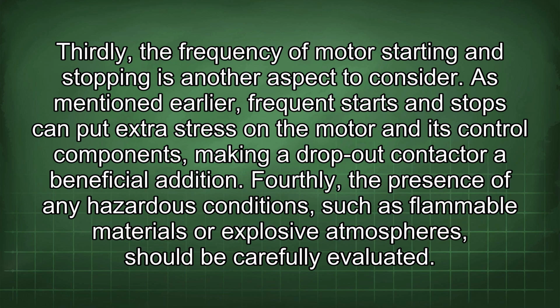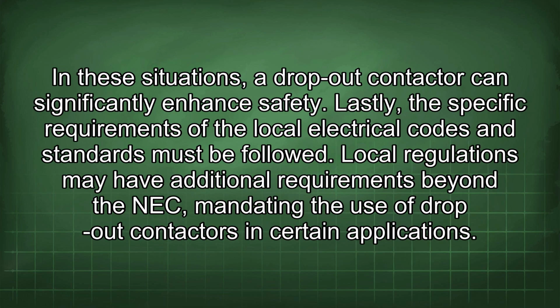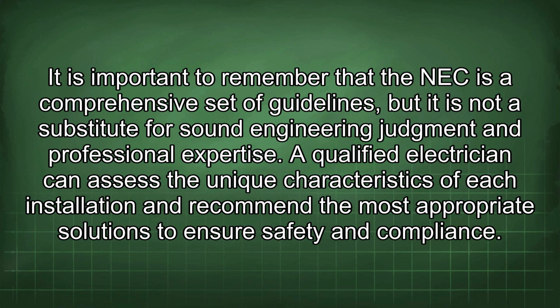Fourthly, the presence of any hazardous conditions, such as flammable materials or explosive atmospheres, should be carefully evaluated. In these situations, a dropout contactor can significantly enhance safety. Lastly, the specific requirements of the local electrical codes and standards must be followed. Local regulations may have additional requirements beyond the NEC, mandating the use of dropout contactors in certain applications. It is important to remember that the NEC is a comprehensive set of guidelines, but it is not a substitute for sound engineering judgment and professional expertise. A qualified electrician can assess the unique characteristics of each installation and recommend the most appropriate solutions to ensure safety and compliance.